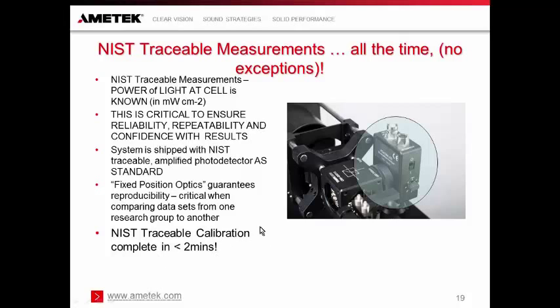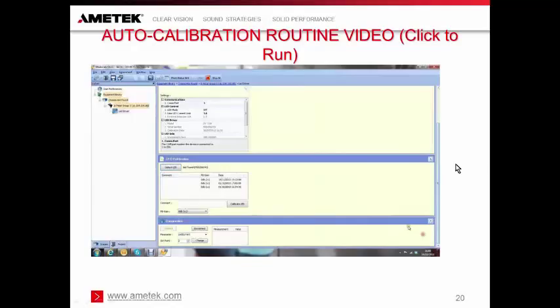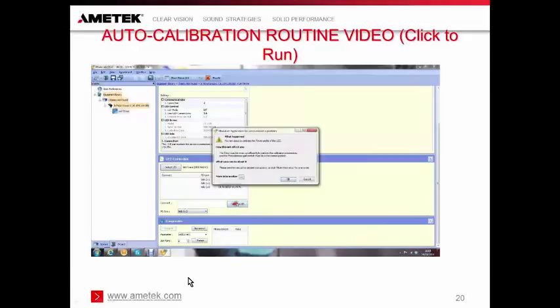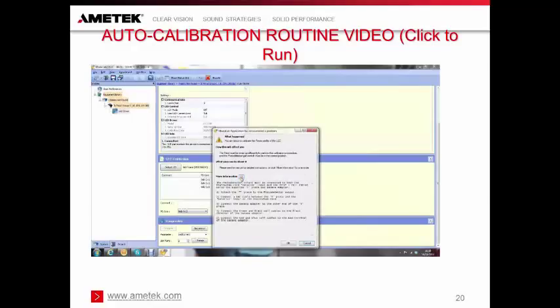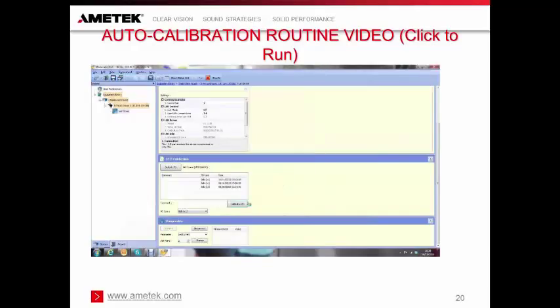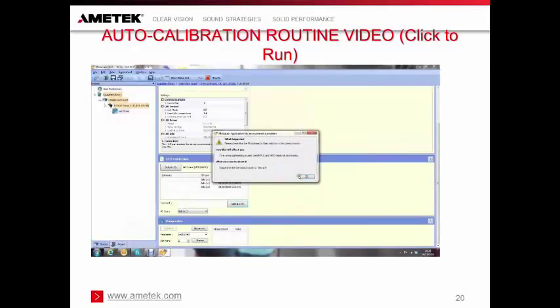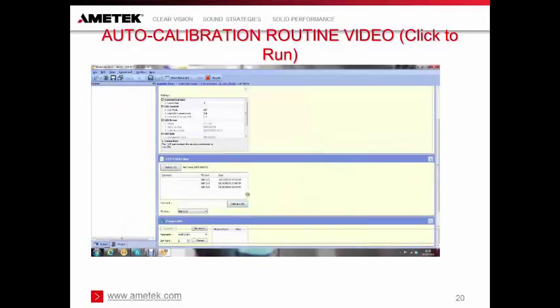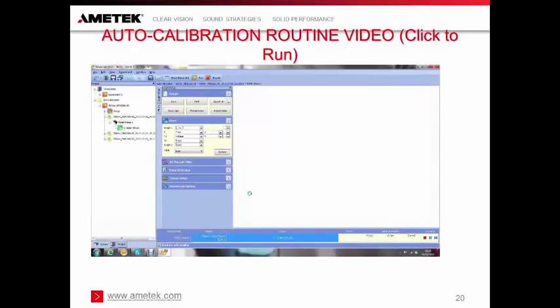Finally, the NIST traceable calibration is complete in less than 2 minutes. And I've got a video to demonstrate this. This is a real-time calibration. This is the calibration screen in the software. And I'll just start the video. So we press Calibrate LED. And the software automatically warns the customer that the system is about to perform a calibration. And it tells this customer how to connect the cables for the calibration. It is a very straightforward process. It also reminds them which gain setting to set on the photo amplifier, and off we go.